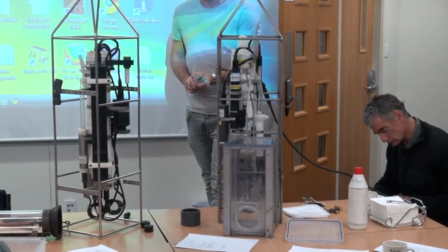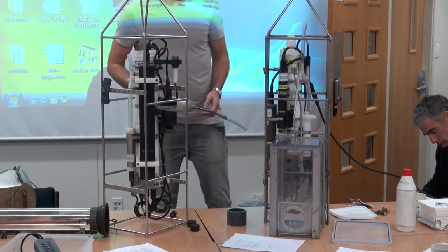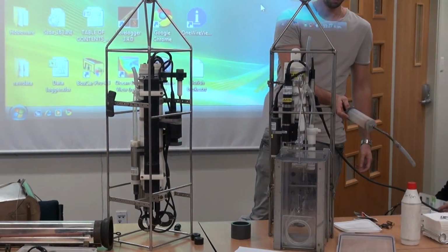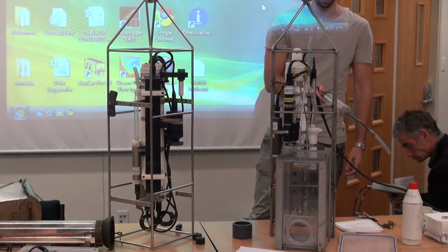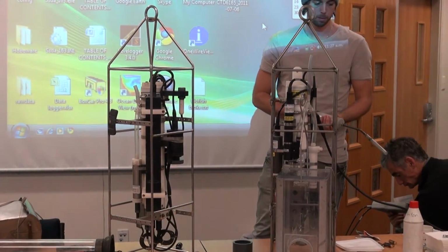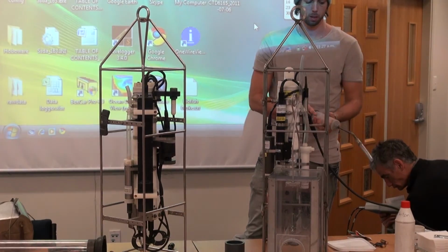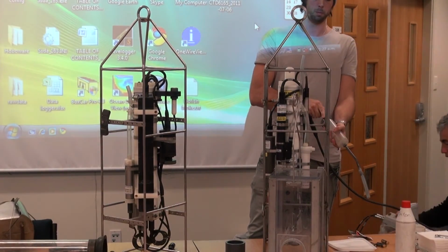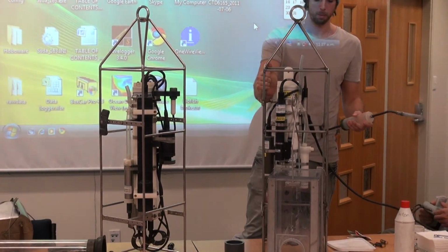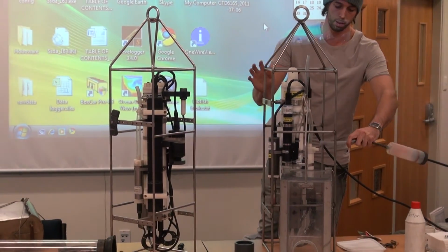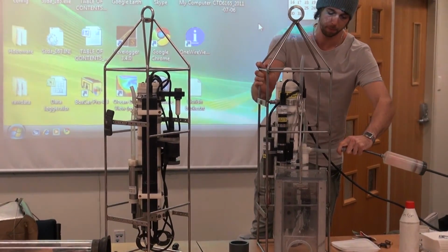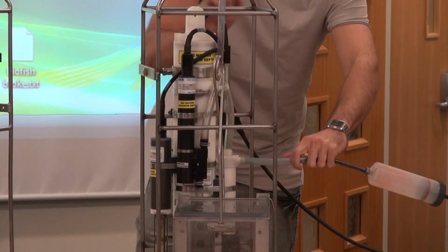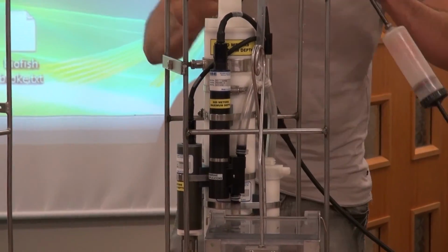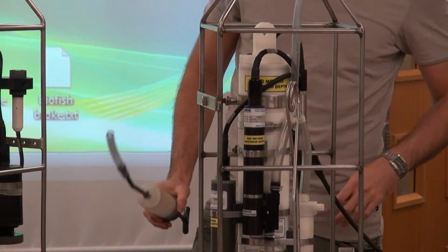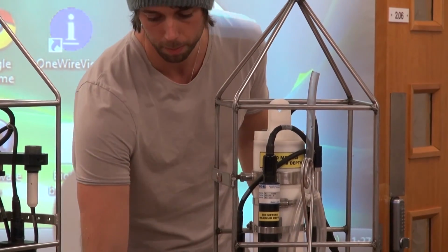we've got these syringe pumps here. Should have your 0.1% Triton and another bottle of just plain old RO water. Do your Triton first, suck some up the pump, and put it over the intake nozzle of the pump, and just force it through. Once with the Triton, once with the RO, and they just get stored like that, dry.